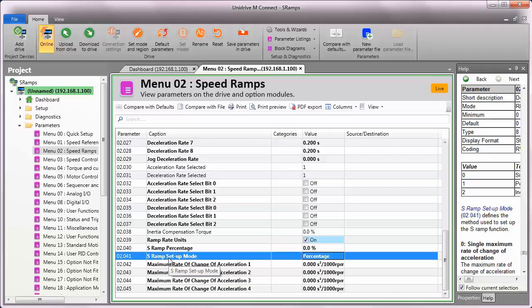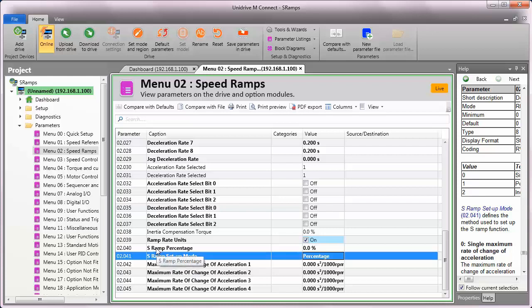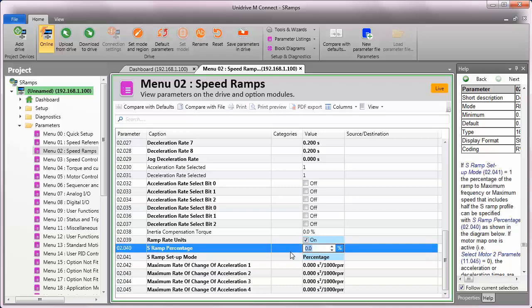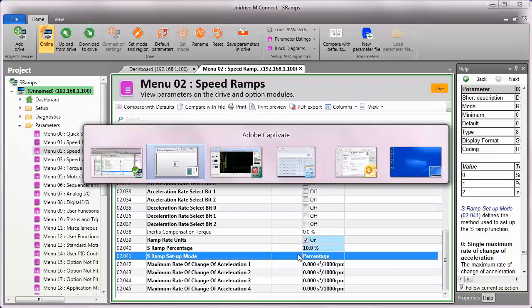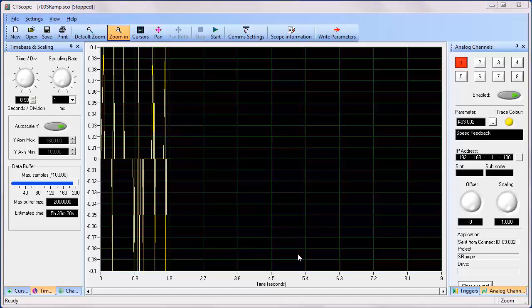Now I'm going to change the value for menu 2, parameter 41, to percentage. This mode works a little differently. In this mode, the S ramp percentage is programmed as a value right here in parameter 40. So by default, it's zero percent, which of course would result in a linear ramp. But if I put a value, for example, of 10% in here, what that's going to do is that's going to use 10% of the ramp as the S portion of the curve. So it's not going to look like much, and I'll just show you this here with CT Scope.